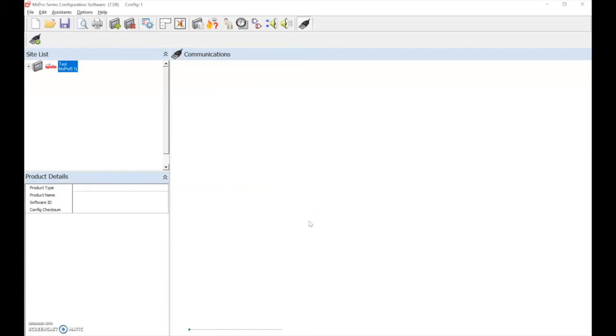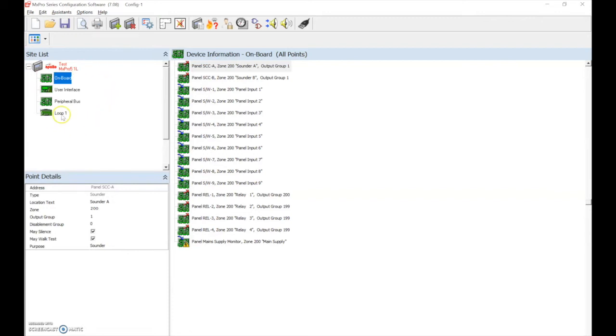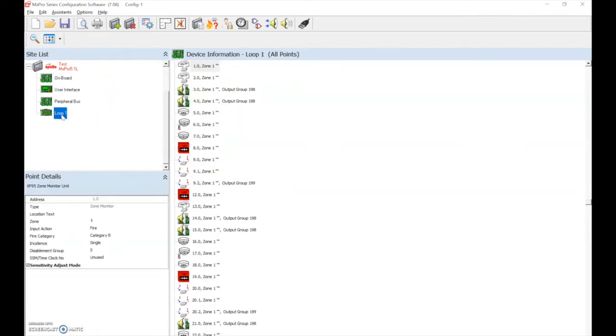Now to achieve the correct functionality of the Fire Cell devices, we need to change the devices to the correct type. We find this in our site list and select the loop on which the devices are on. After the auto-learn has been performed, the panel will find the devices and add them in as XP95 type devices. To achieve the correct functionality, we must change these to the wireless type devices.